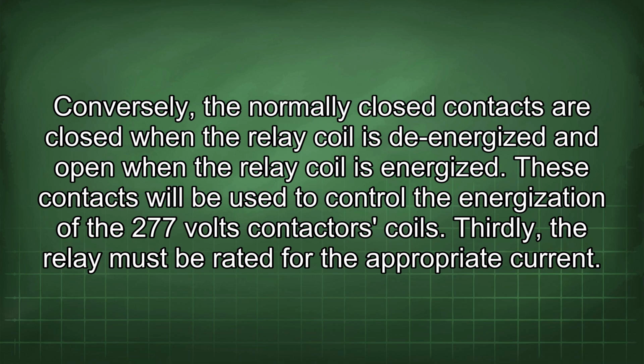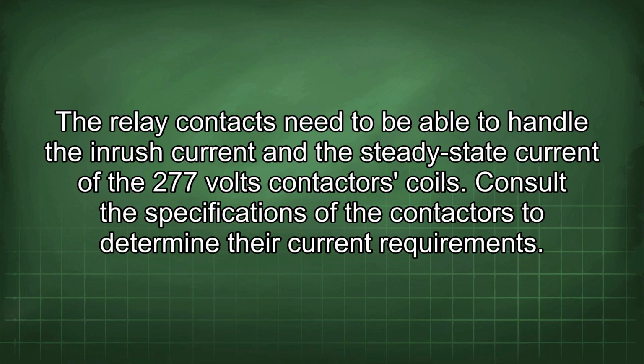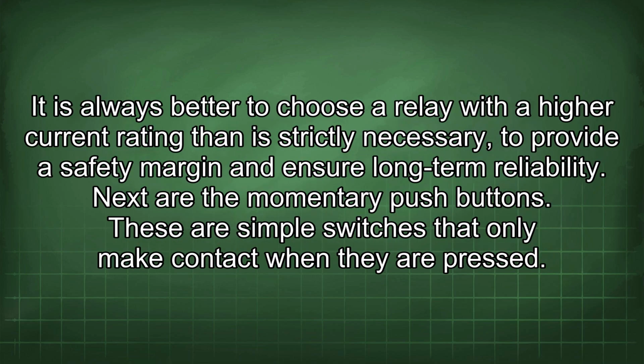Thirdly, the relay must be rated for the appropriate current. The relay contacts need to be able to handle the inrush current and the steady-state current of the 277 volts contactors coils. Consult the specifications of the contactors to determine their current requirements. It is always better to choose a relay with a higher current rating than is strictly necessary to provide a safety margin and ensure long-term reliability.